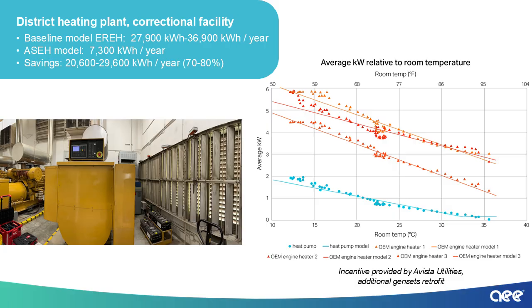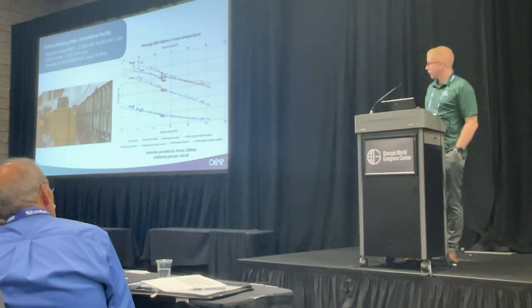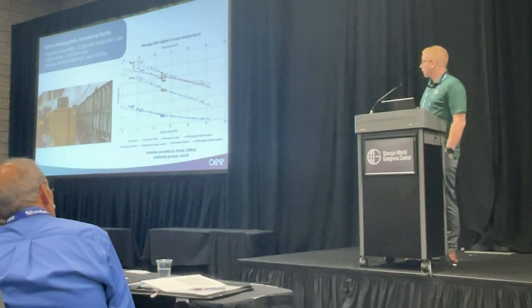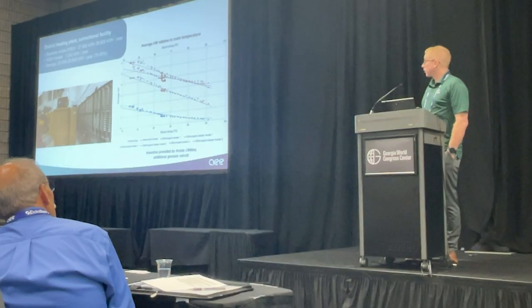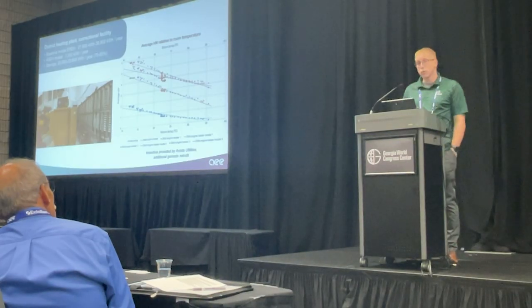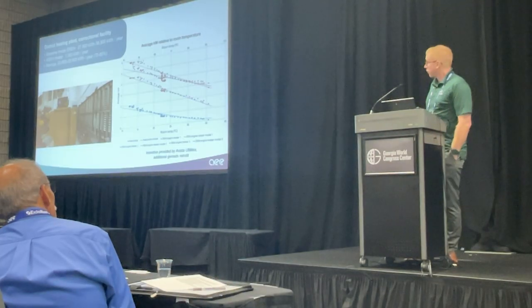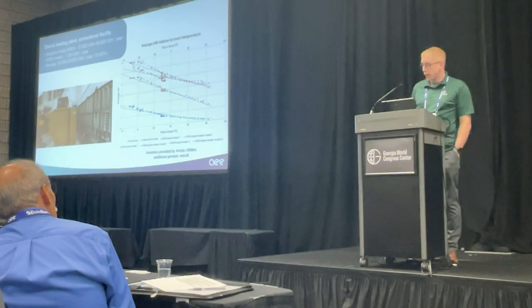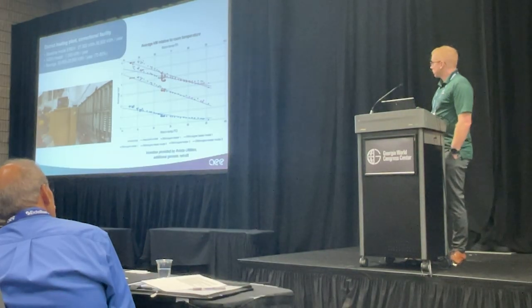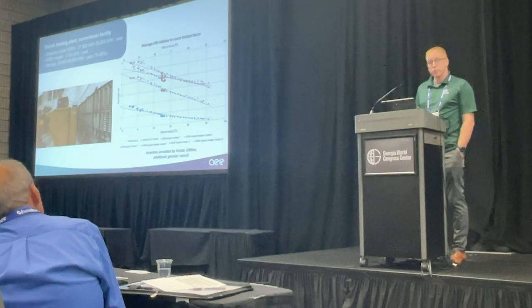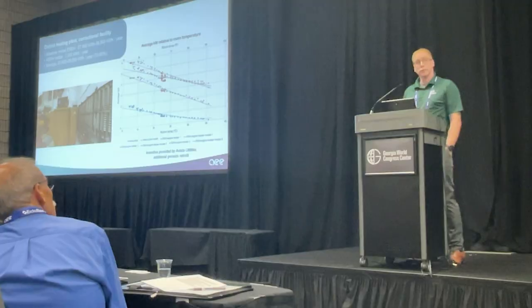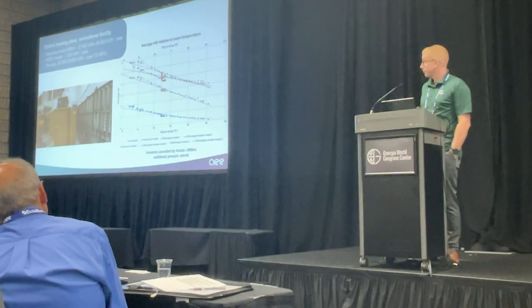They each had different types of electric resistance engine heaters, from pump driven to thermosiphon. And then there was the one engine that was retrofit with a single speed air source engine heater. This is the energy usage for that. As we apply that to the local weather in that location, energy savings were between 20,000 and 30,000 kilowatt hours per year, based upon the models for the 3 different engines. And again, incentive was provided by Avista for this location.